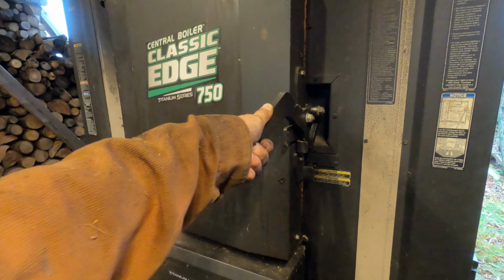Anyhow, that'll basically wrap it up. We're at 120. I run this at 185 in the warmer temperatures, say spring and fall. I'll run it at 190 as the set point temperature in colder weather, because when it does shut off, it overshoots a little bit. So at 185, when it shuts off, if there's nothing calling in the house, the temperature may rise up to 190 or slightly more. So I don't want to set the temperature too high and have it do a high temperature shutdown or something like that.